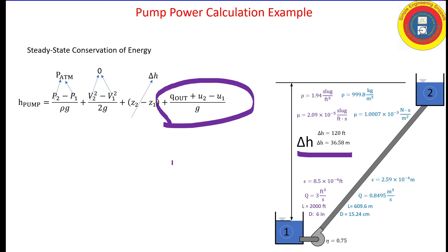We're still left with this grouping of terms on the far right-hand side. We are going to determine the head loss term. My head of the pump in this situation is equal to the change in elevation plus the head loss. That's the amount of energy per weight that the pump must supply to the fluid for it to be operated under the provided conditions.